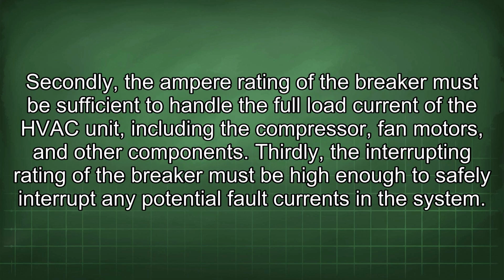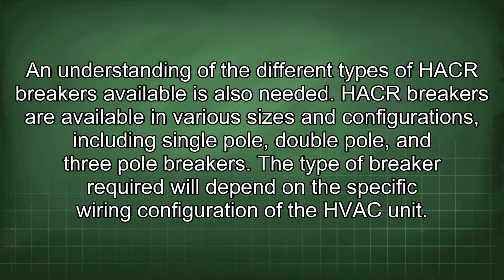Secondly, the ampere rating of the breaker must be sufficient to handle the full load current of the HVAC unit, including the compressor, fan motors, and other components. Thirdly, the interrupting rating of the breaker must be high enough to safely interrupt any potential fault currents in the system. An understanding of the different types of HACR breakers available is also needed.